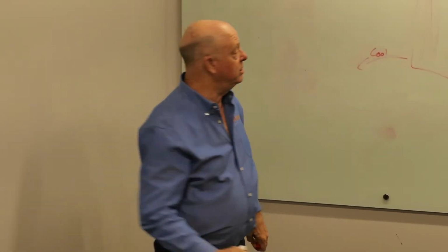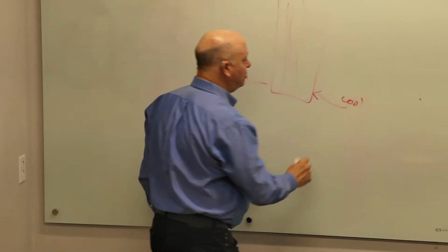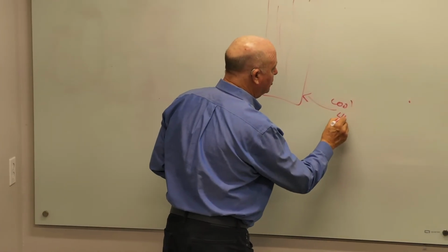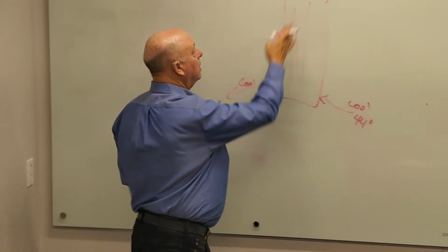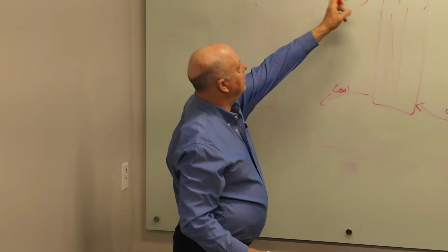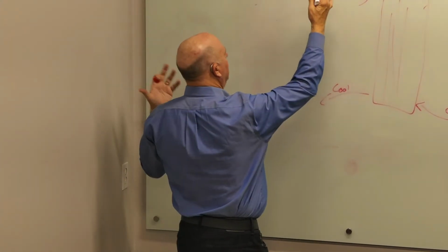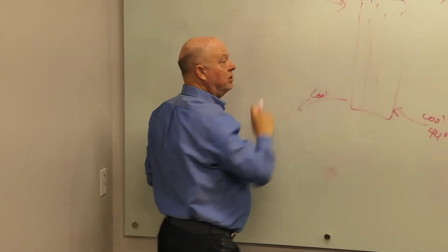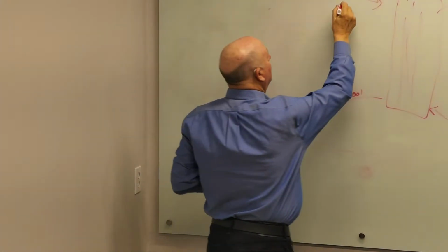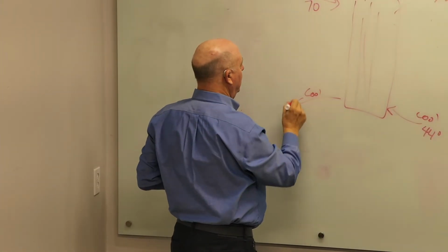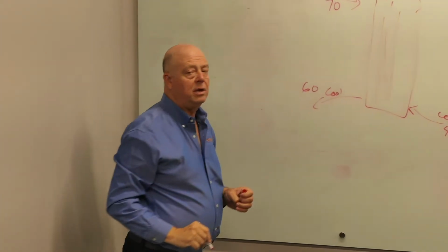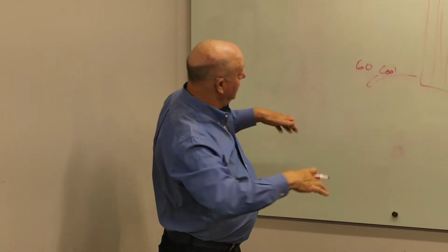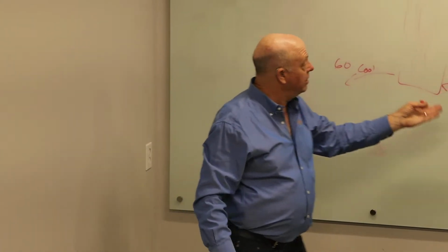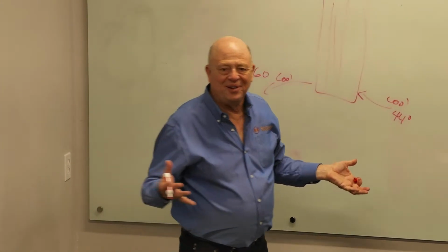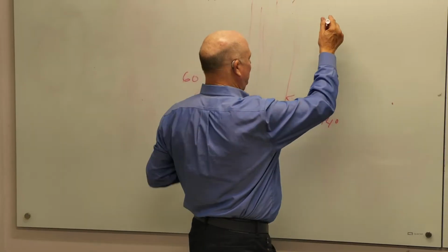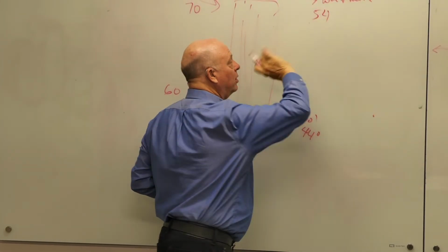And the reason is, let's say we were putting in 44-degree chilled water, and let's say that this was some processed liquid, I don't know. And we're putting 70-degree water in, and we want it to come out at 60. And if we had equal flows and we cooled this by 10, then we're probably going to raise that one by 10. It's just the math if the flows are the same. So now we're out at 54 and we're going back to our chiller.